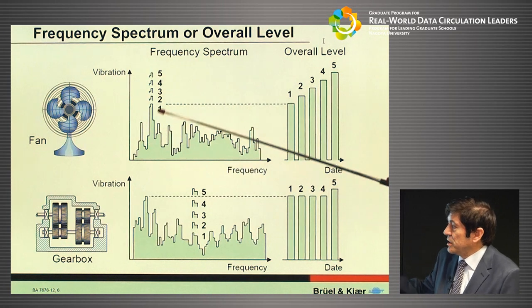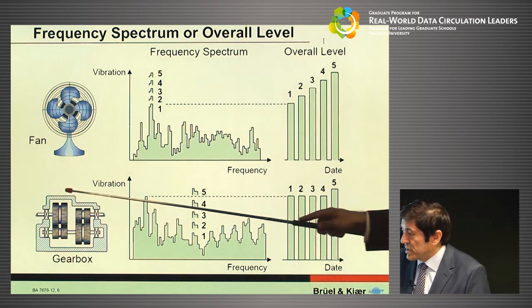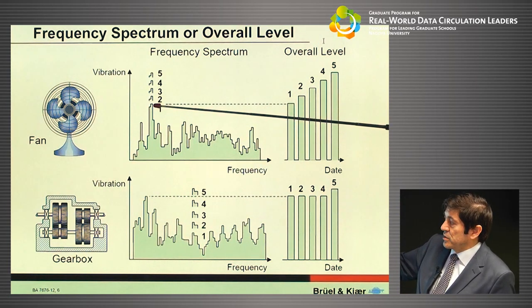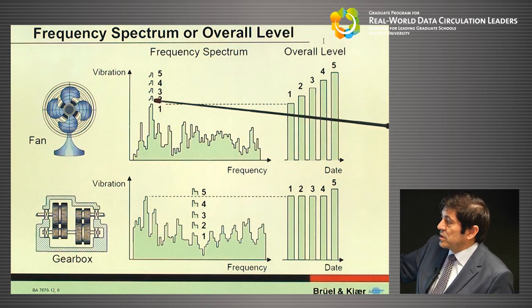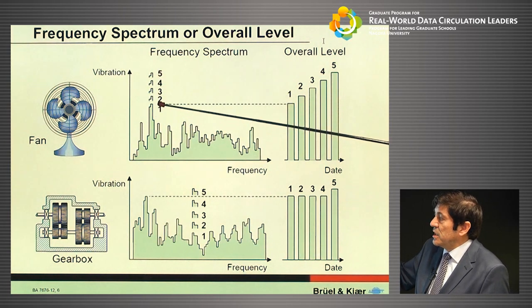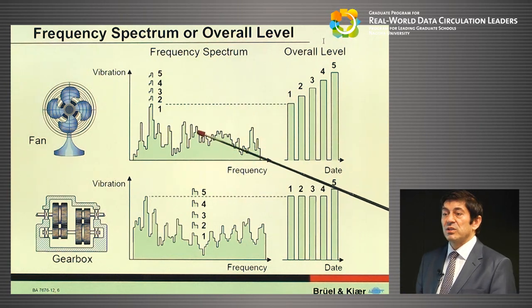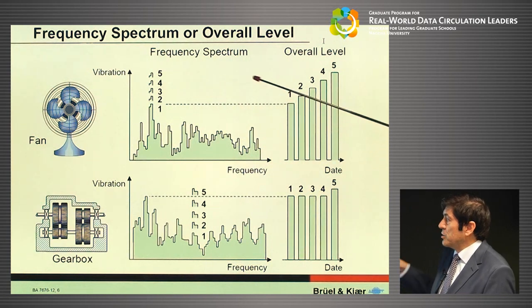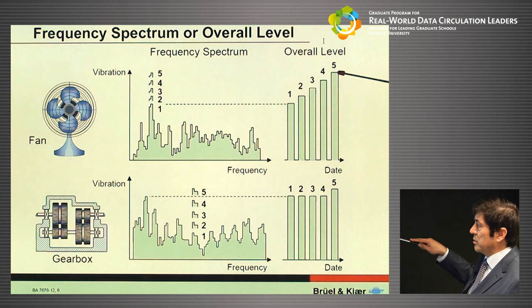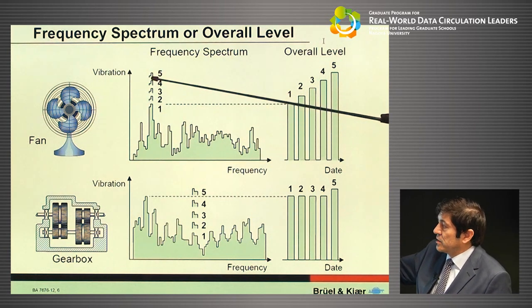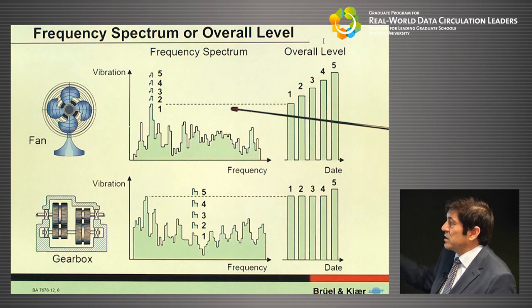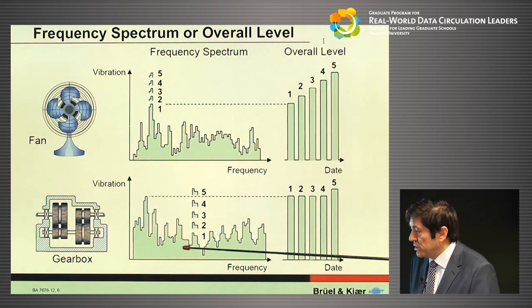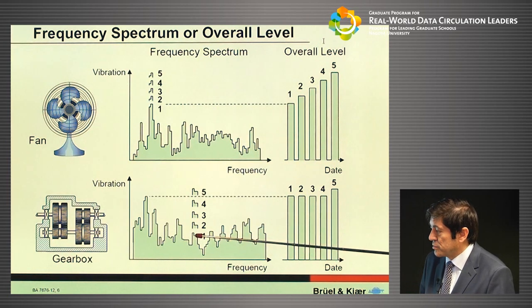A fan has this spectrum. This is a gearbox. The gearbox has this spectrum. For instance, we have a peak value at this point. Then this peak value is increasing in time. It means there is something getting older, or wearing out in time. So the overall level is increasing in time. By just looking at this peak in frequency domain, we can make a conclusion about the condition of the fan.